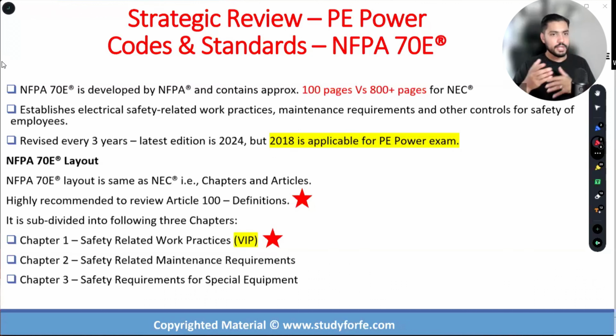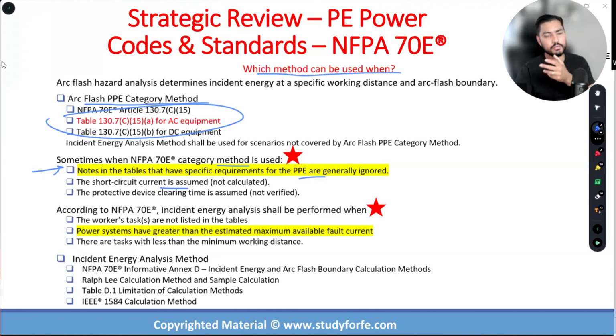But the issue is that even when we are using the category method, notes in the table that have specific requirements are generally ignored in practice. Sometimes you have assumed values, not the actual calculated values, and that goes for even the protective device clearing times. So if you want a rough ballpark, this is not a bad place to start. If you have accurate details that are matching perfectly, then go for it.